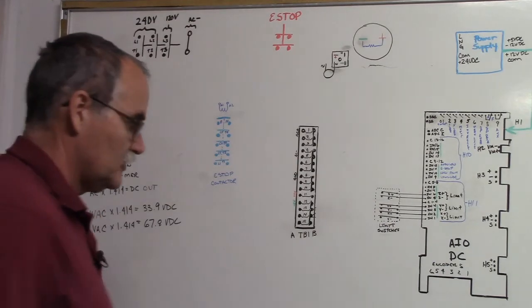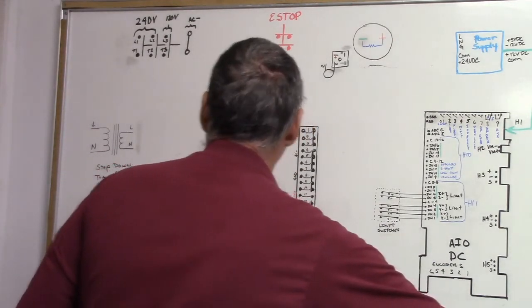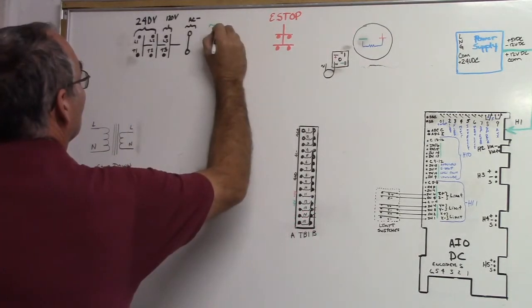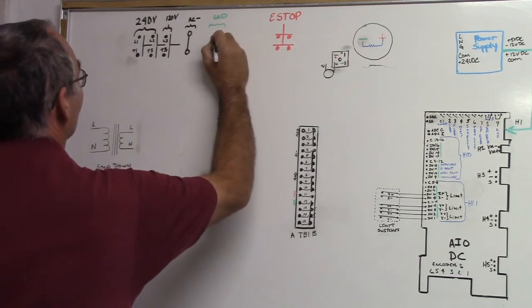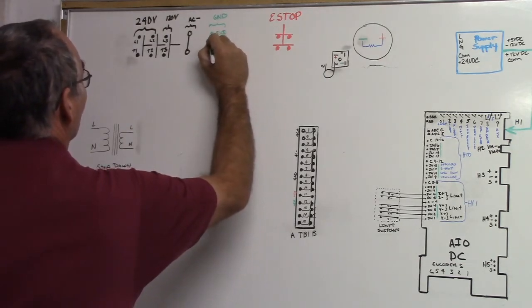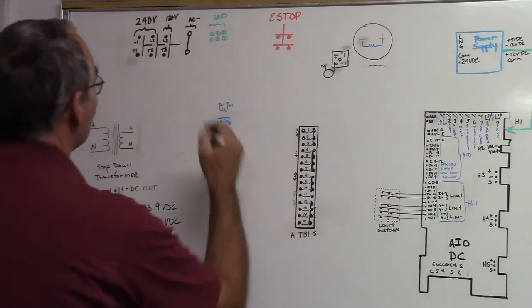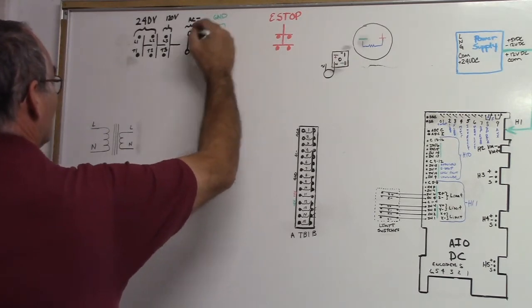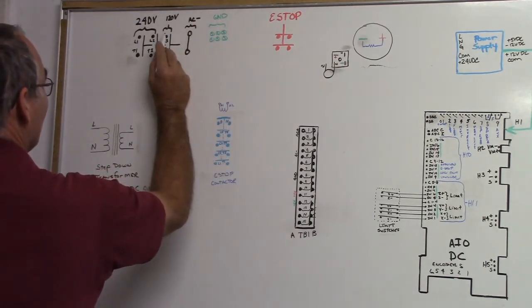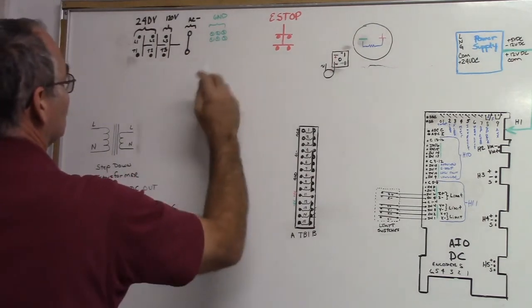So the best practice, here's your chassis ground, the best practice is to have one point to bring all your grounds to. In this case they bring them here. Your cables are going to come in, your AC line cable, 120 volt cables come in. You're going to have AC plus or line, negative, and ground.